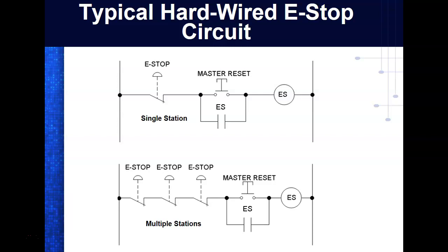Did I tell you a story out at US Steel? We had like 50 e-stops on one of the lines out there. This thing was 3 stories high. It was where they ran the strip, and we'd have guys that wanted to take a break, and they'd be up here and they'd do what? They'd hit one of those e-stop buttons, and the line would shut down, and they would have to go over every one of those stations and find the e-stop. So we came up with a light panel. We had a big light panel, with one LED or one light per e-stop. So if they were hitting e-stop, that light would go out.